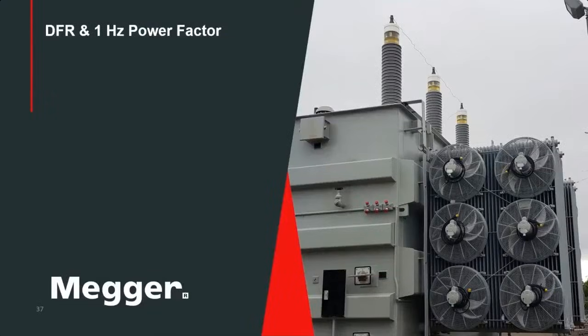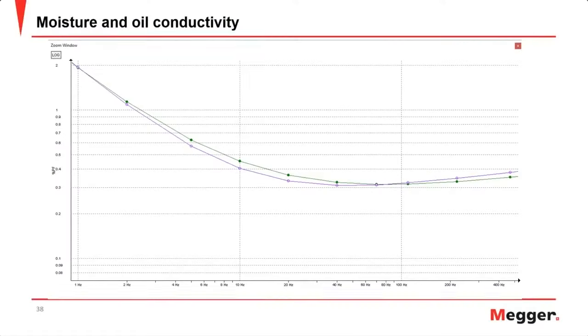Next, we want to look at some advanced tests. The first being dielectric frequency response, and then how 1 Hertz power factor fits into this. So earlier, I talked that when you change voltage, your power factor should not change, and that is correct. When you change temperature, your power factor should change. That is correct as well. And the last truth about insulation, and I'm sure there's more to come many years after this, but the one that we focus on today is that when you change frequency, power factor also changes.